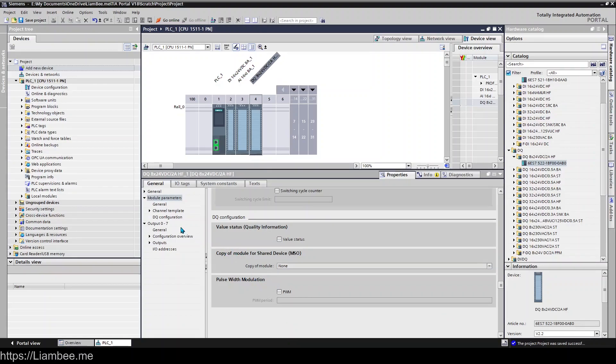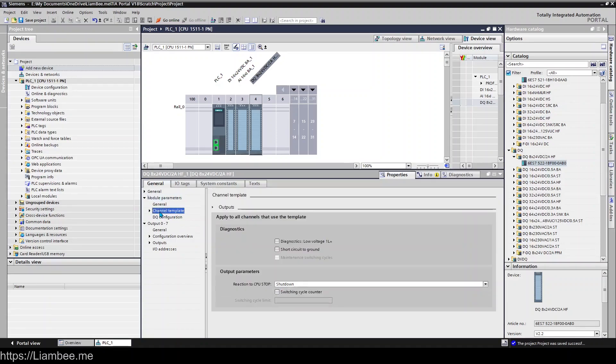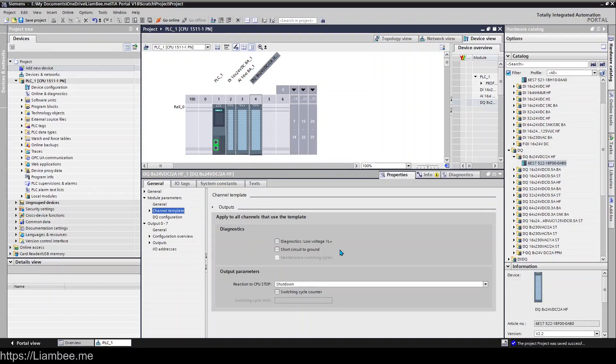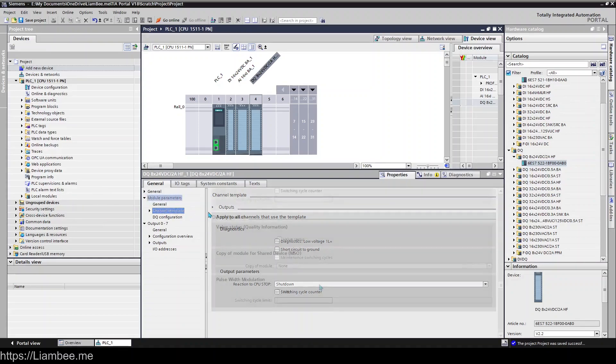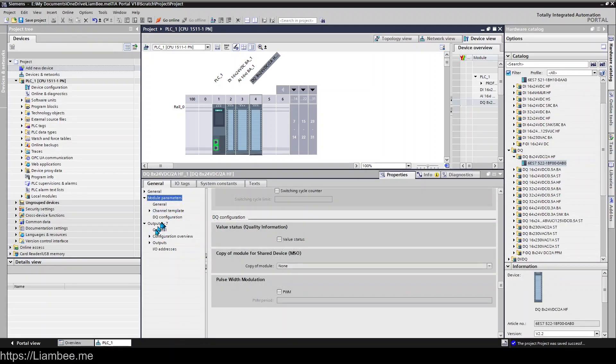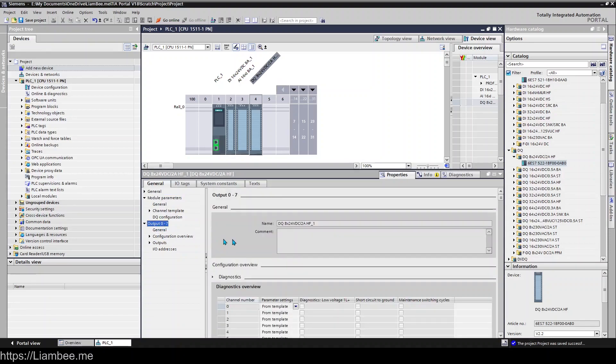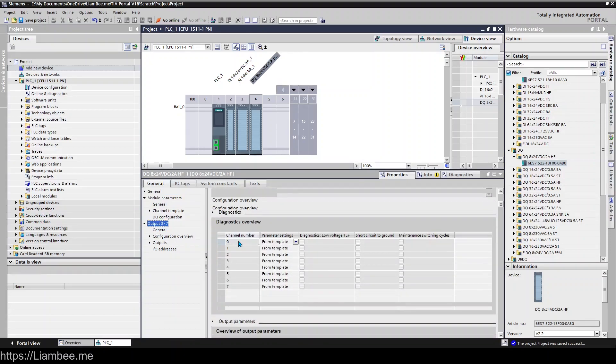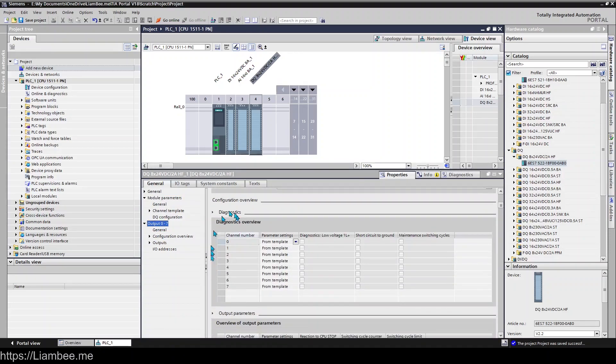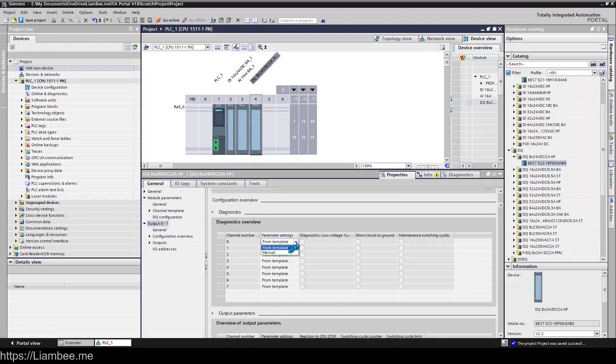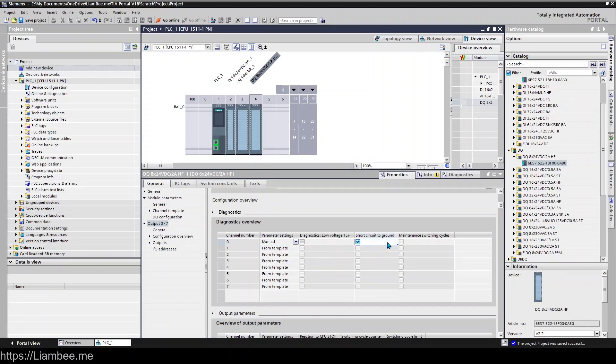If we have a look at the channel template, which suggests that we can set this for individual ones, so if we have a look at outputs 0-7 here, we can see that we have diagnostics overview, parameter settings from template, or you can go ahead and set it manually. So we could say we only want to detect a short circuit to ground on channel zero, but for the rest of them we're not interested in doing that.